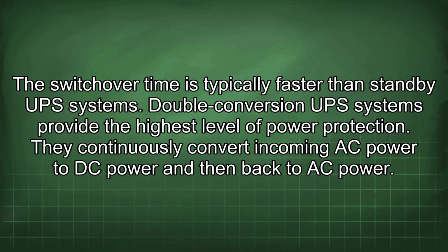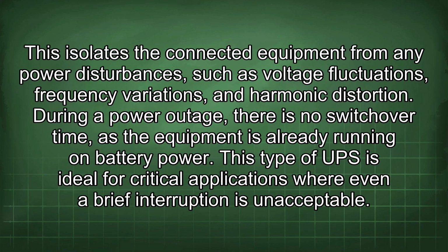Double conversion UPS systems provide the highest level of power protection. They continuously convert incoming AC power to DC power and then back to AC power. This isolates the connected equipment from any power disturbances, such as voltage fluctuations, frequency variations, and harmonic distortion. During a power outage, there is no switchover time, as the equipment is already running on battery power. This type of UPS is ideal for critical applications where even a brief interruption is unacceptable.